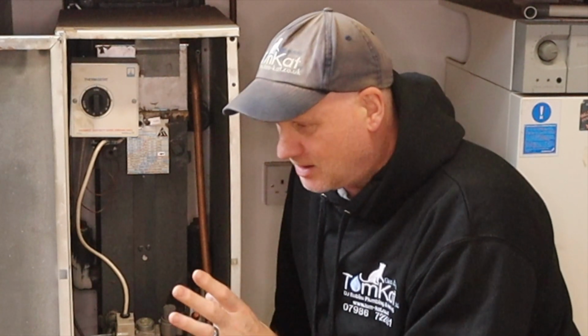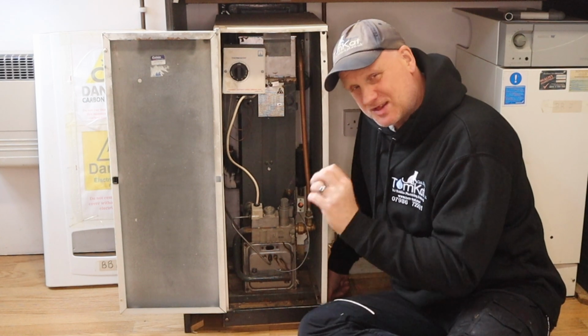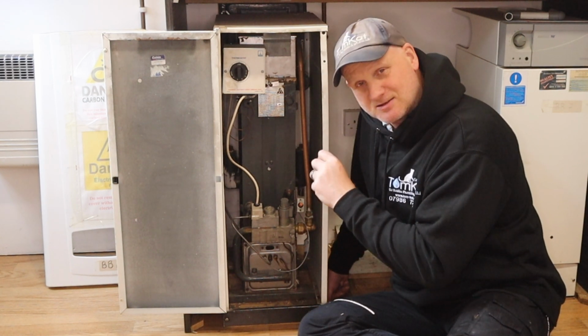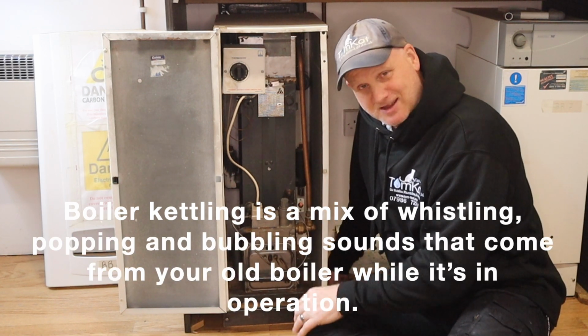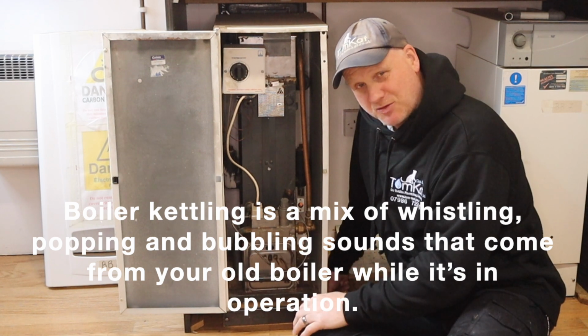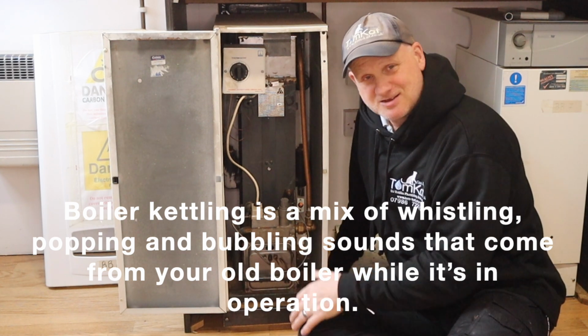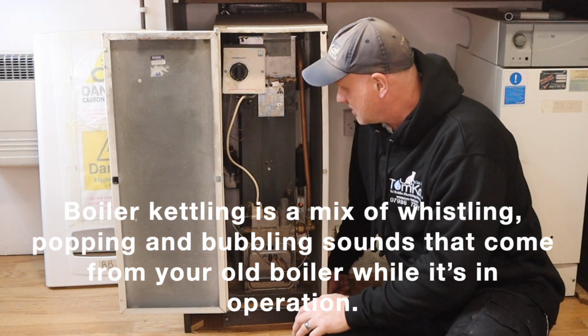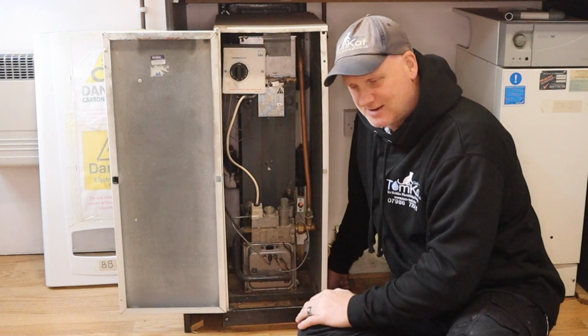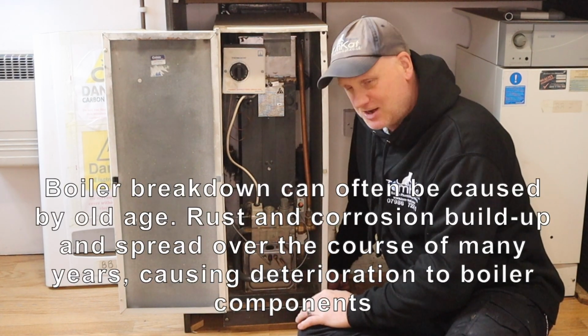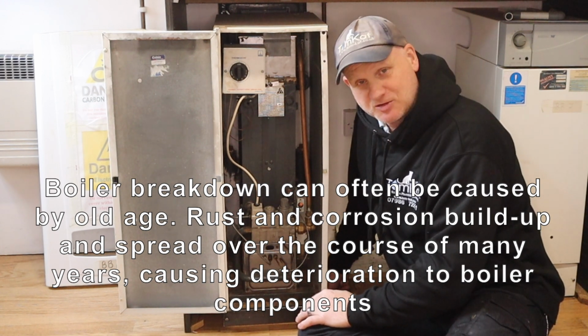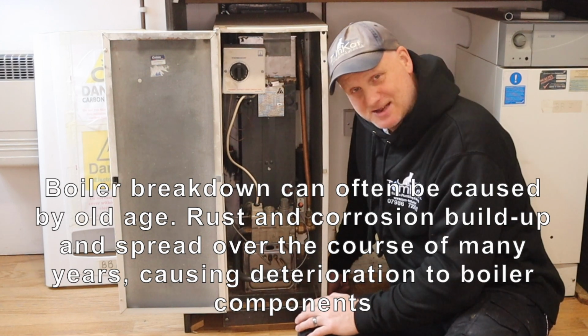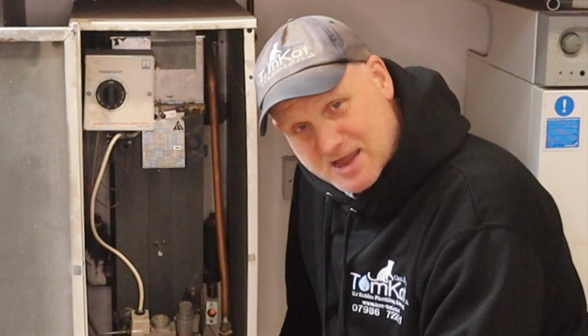Actually, if your boiler is that old, like this one is over 30-40 years old, then it might not be cost effective to keep it running, and it will save you more money replacing it. This boiler, if you ever listen to it actually run, it kettles that mad, it's probably down to about 30-40% efficient rather than a new condensing boiler which should be 92% efficient. So if your boiler does look like this one, then my advice will be get rid of it and get a new one if you can afford it. And if you can't afford to do that, keep your fingers crossed that it doesn't break down over these winter months, because we might not be able to repair them.